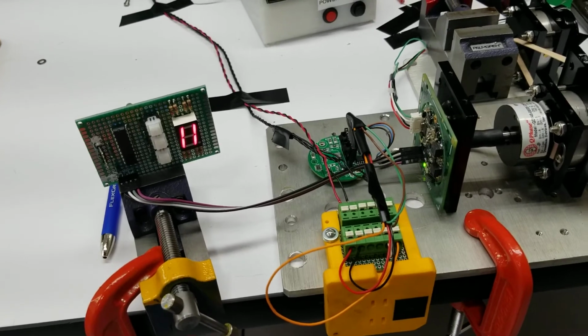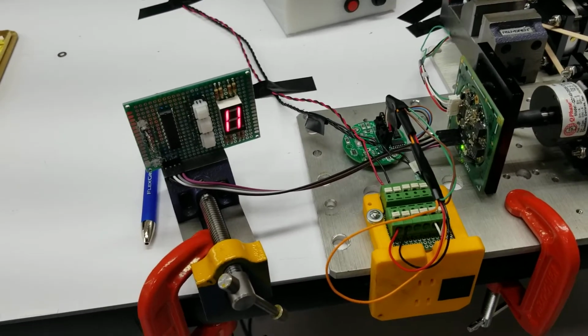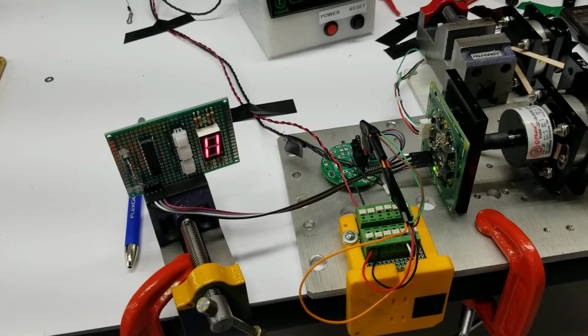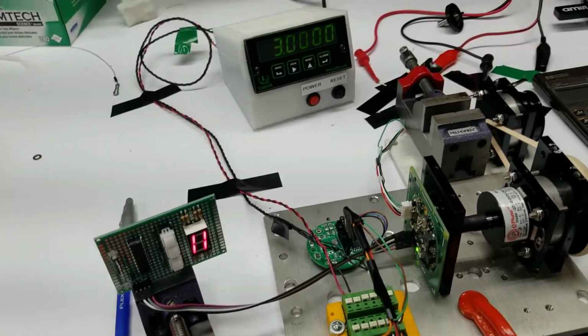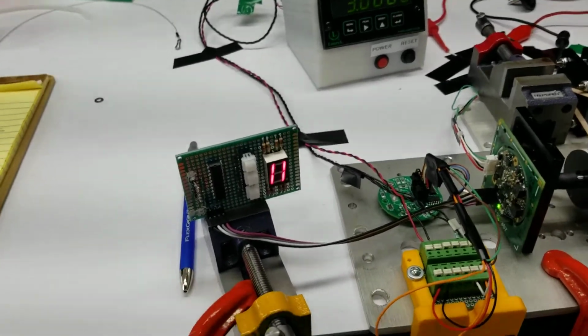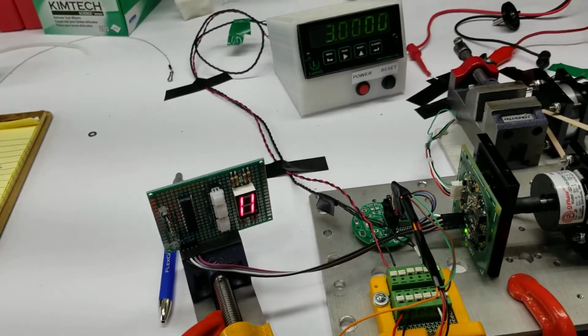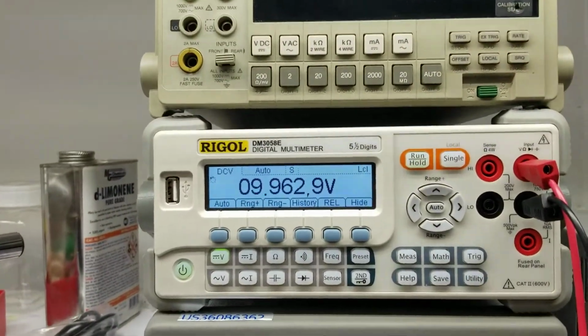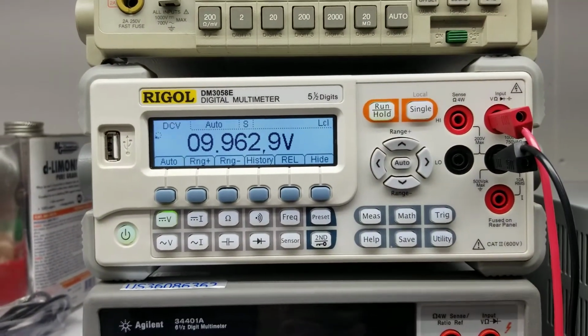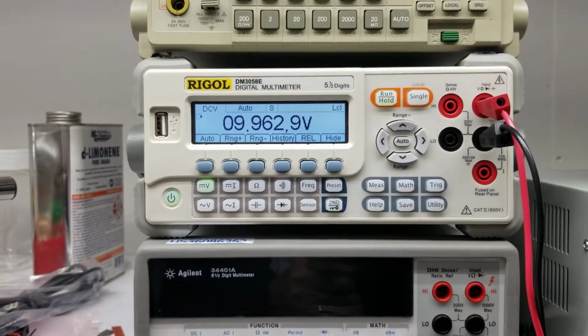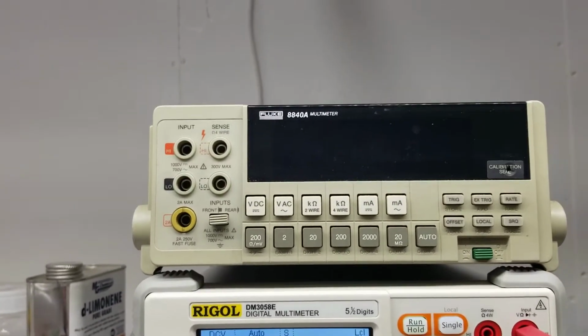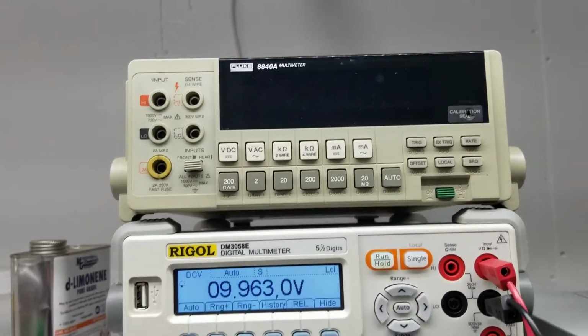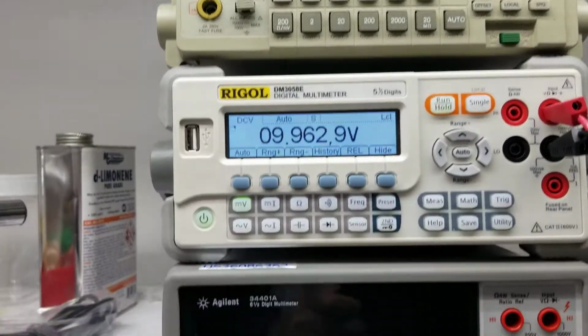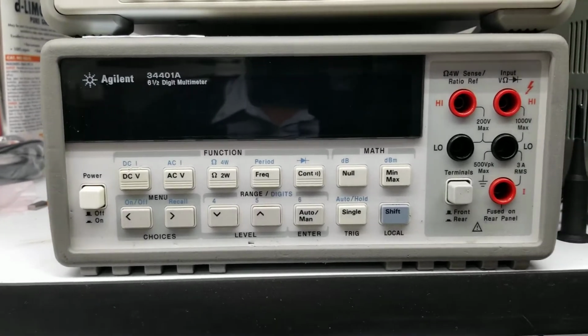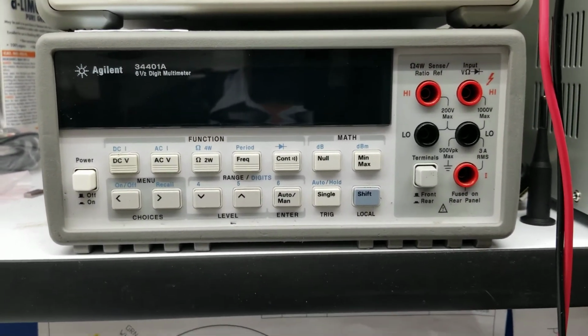I wanted to demonstrate an anomaly here that I've discovered when setting the maximum voltage out on the unit. So I've got the turns rotating. I've got the turns programmed in. I'm going to set up the turns. I'm running everything into this meter. This is a Rigol meter, which I just bought and received about a week ago. I have compared it to this 25-year-old or so Fluke 8840A, and also to this NIST traceable Agilent meter, which is what we use for calibrating our transducers.